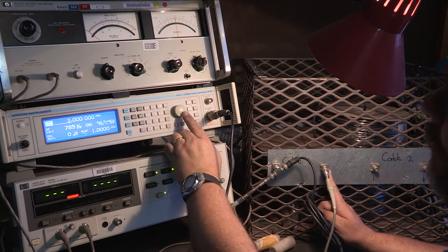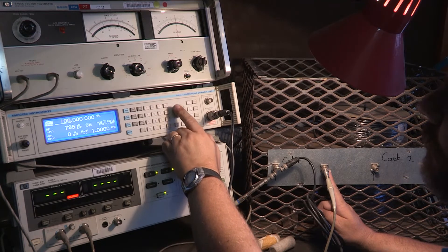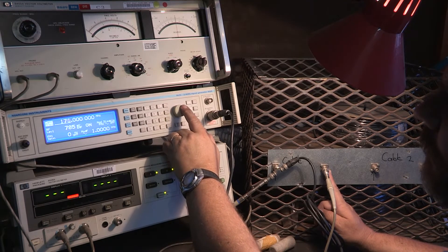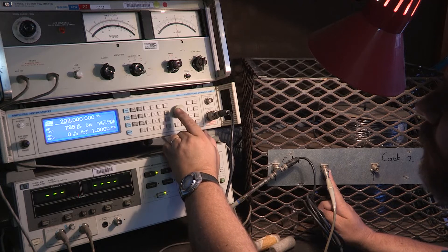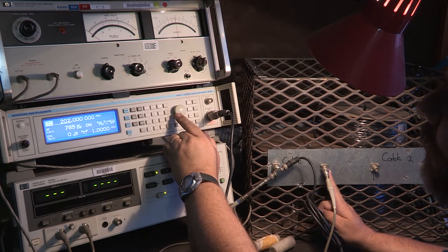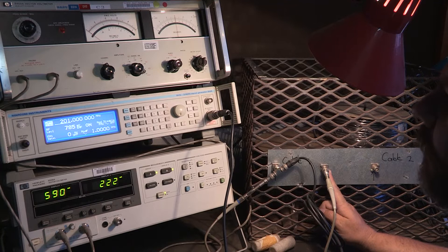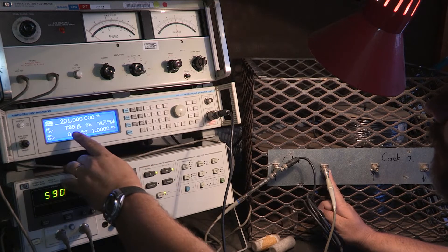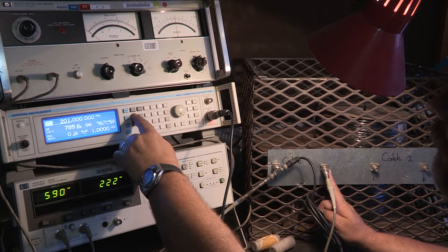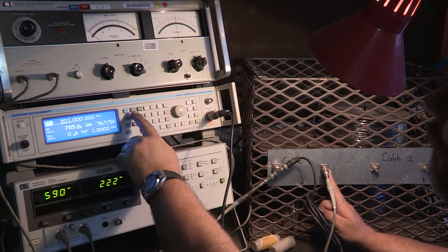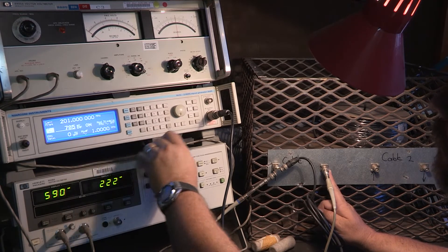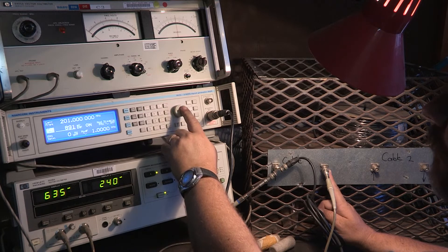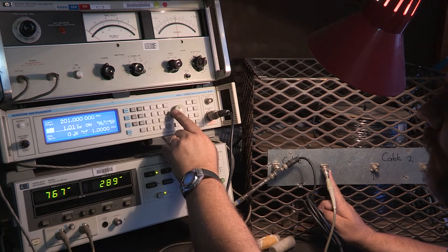If I go back and change my carrier frequency, you'll notice the instrument on the vector voltmeter is adjusting. Just for demonstration purpose right now, if I choose a frequency like 200 megahertz, I need to adjust the RF level so that we can get back to 730 millivolts.